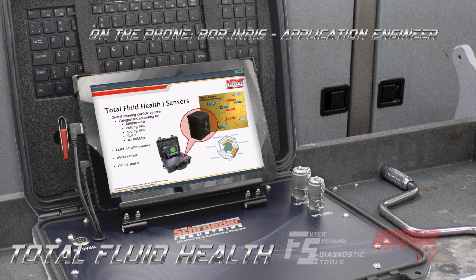What it can do is, with a set of algorithms incorporated into the software, the sensor can recognize the general shape of the particle as it's passing through the sensor cell, categorize those particles into the individual categories, and subtract the air bubbles from the particle count, which is important because previous technologies don't handle aeration very well, not without some good support.